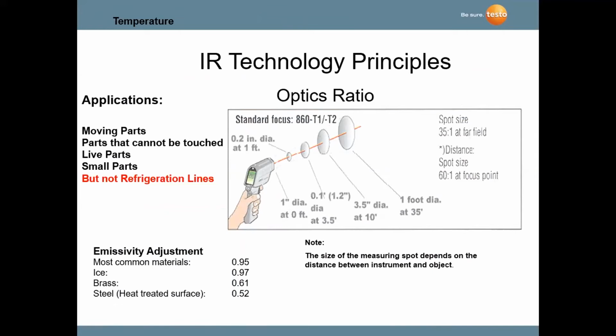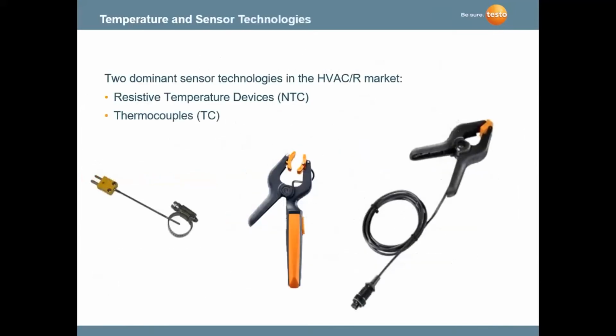And one thing, as we get into the instrument side of this, everyone probably has an infrared thermometer, and infrared thermometers are a great tool for looking at primarily only surface temperature. If you point an infrared thermometer at a supply duct or return, you're not getting the air temperature. You're getting the surface temperature of the grille itself. So keep that in mind. And these are not to be used on refrigeration lines. What we're using today are pipe clamp probes, obviously.